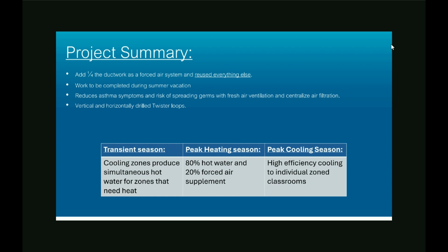So right now, it's October, so kind of a transient load period. And so you might have some zones that are in cooling and some that are simultaneous heating. In that case, the equipment can produce simultaneous chilled air and hot water, which can be used in other zones. It could be stored. During the peak heating season, we would cover the load by 80% hot water, 20% supplemental hot air.